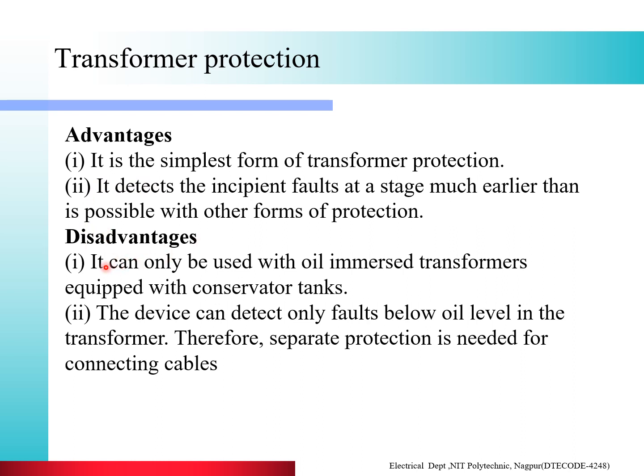The disadvantage is it can only be used with an oil immersed transformer equipped with a conservator tank, because this Buchholz relay is a gas operated relay, and it is only used in the oil immersed transformer, because its function is basically based on the evaporation of the oil, which gets converted into gas. So where an oil immersed transformer is there, only then can you use this relay.